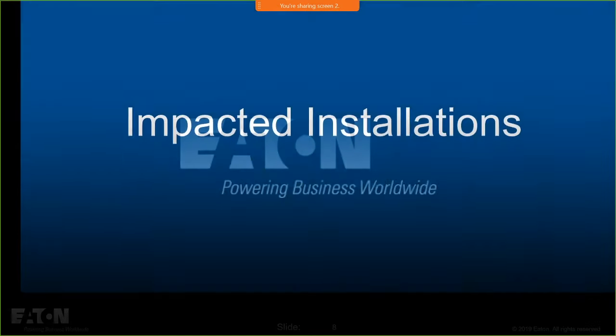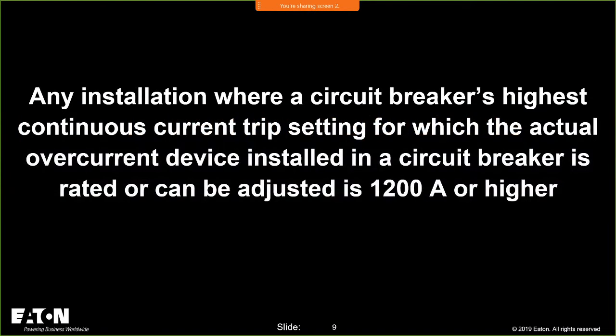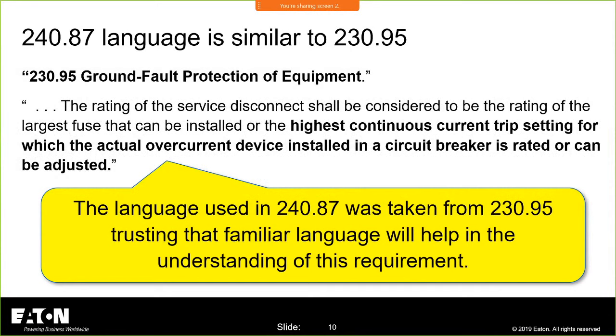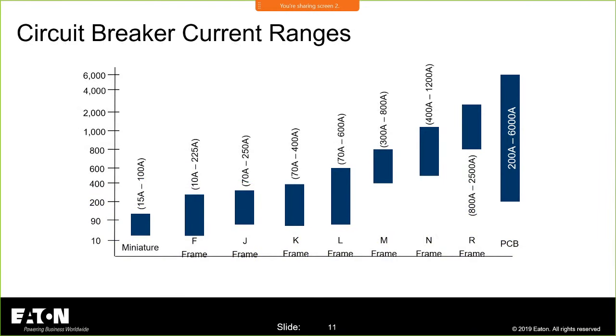Let's talk about the impacted installations. Any installation where a circuit breaker's highest continuous current trip setting, for which the actual overcurrent device installed in a circuit breaker is rated or can be adjusted, is 1200 amps and higher. So that tells us that if I have a 1200 amp frame and I adjust it down to 600 amps, I still need to employ it because I can adjust it up to 1200 amps. Now, during the code cycle, I presented to Code Making Panel 10 this graph to help them understand the impact of what they were talking about.